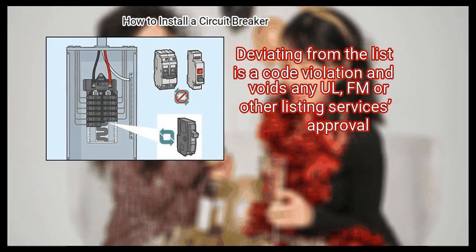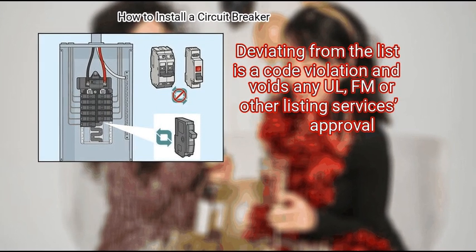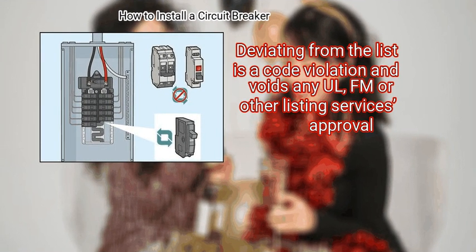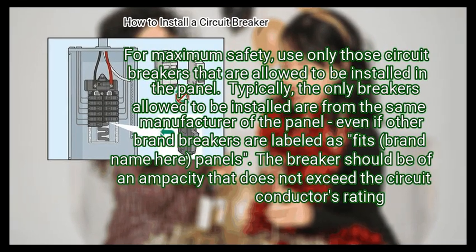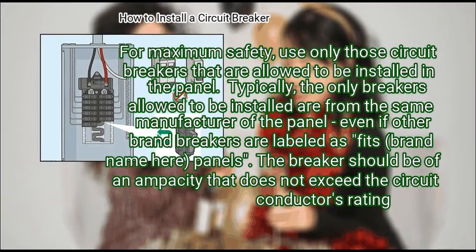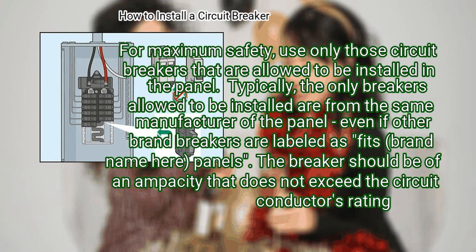Deviating from the list is a code violation and voids any UL, FM or other listing services approval. For maximum safety, use only those circuit breakers that are allowed to be installed in the panel. Typically, the only breakers allowed to be installed are from the same manufacturer of the panel, even if other brand breakers are labeled as fits. Brand name here, panels. The breaker should be of an ampacity that does not exceed the circuit conductors rating.